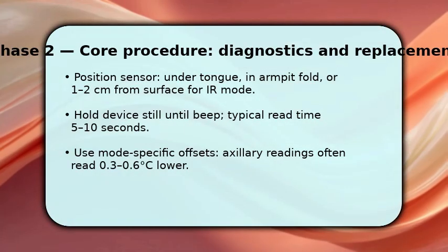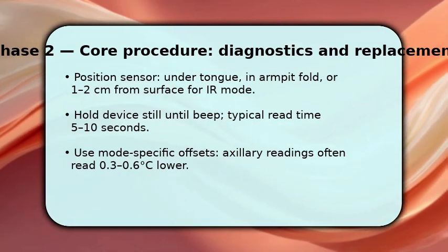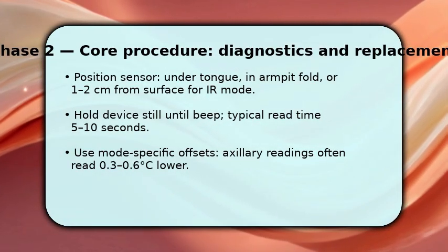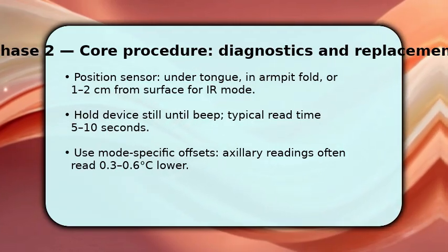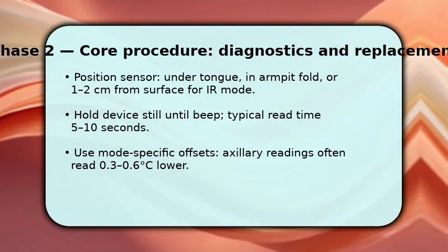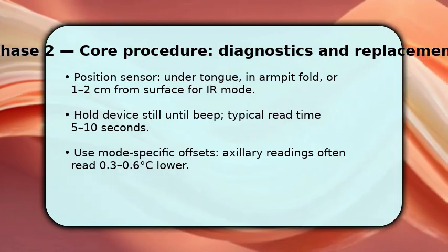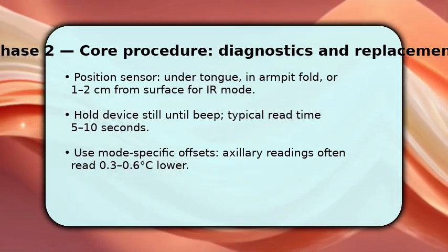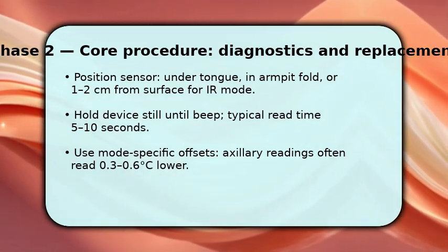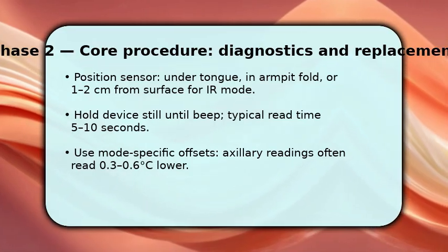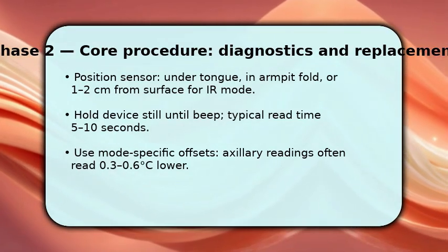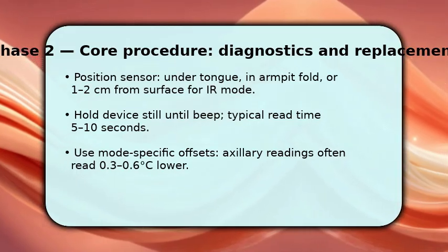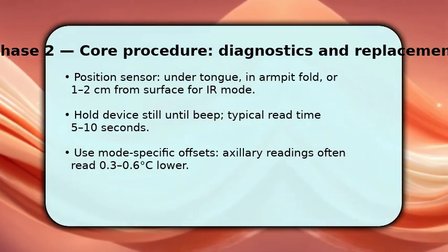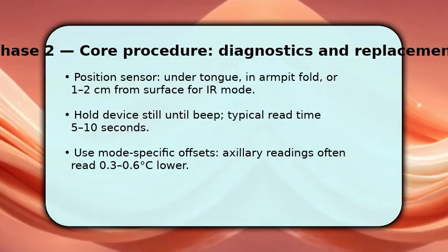Now place the probe correctly for the chosen mode, under the tongue toward the back for oral, tucked well into the armpit for axillary, or aimed at the center of the forehead for IR surface readings. Hold the thermometer steady. Movement causes variance, so keep still until the beep signals a full read. This takes about 5 to 10 seconds. After the beep, wait a moment before removing, because transmission stabilizes. Make sure to apply mode-specific offsets when comparing to clinical standards.